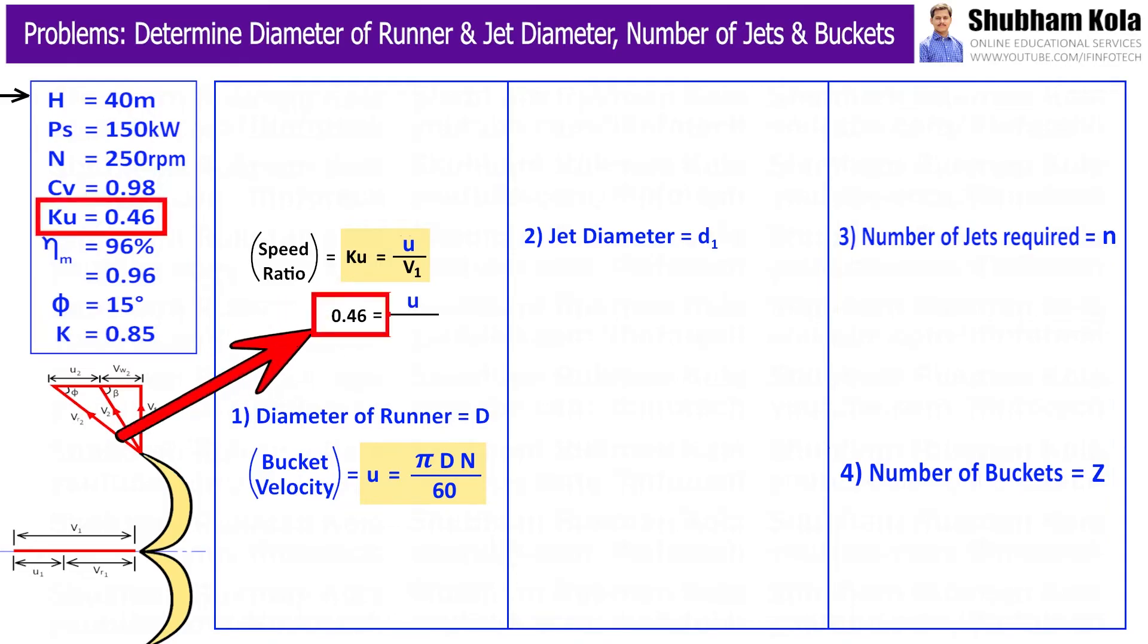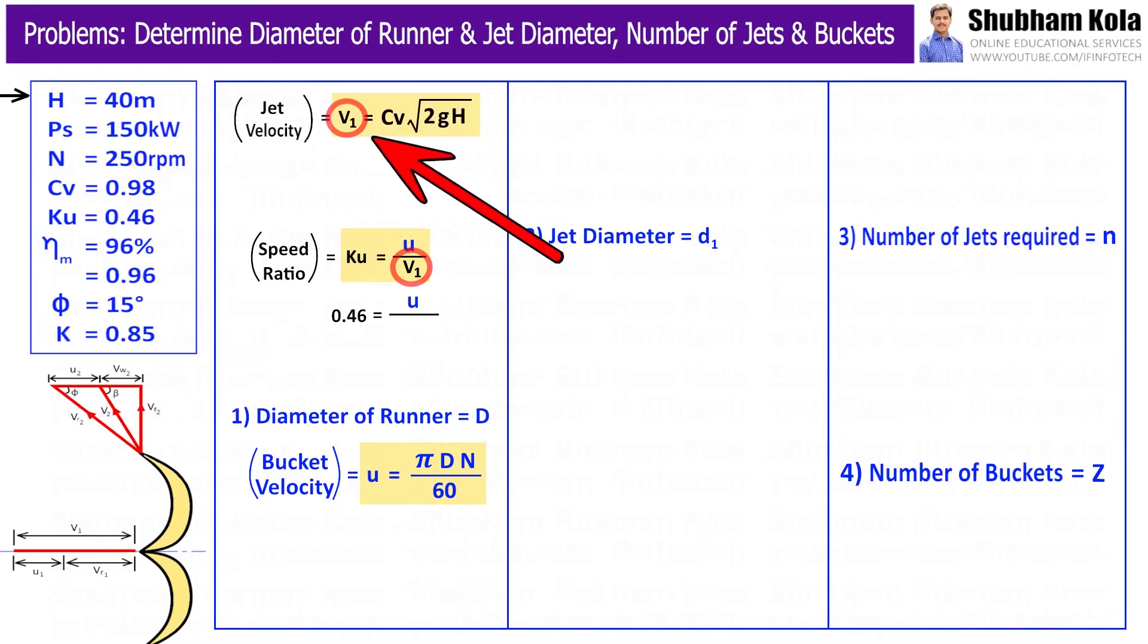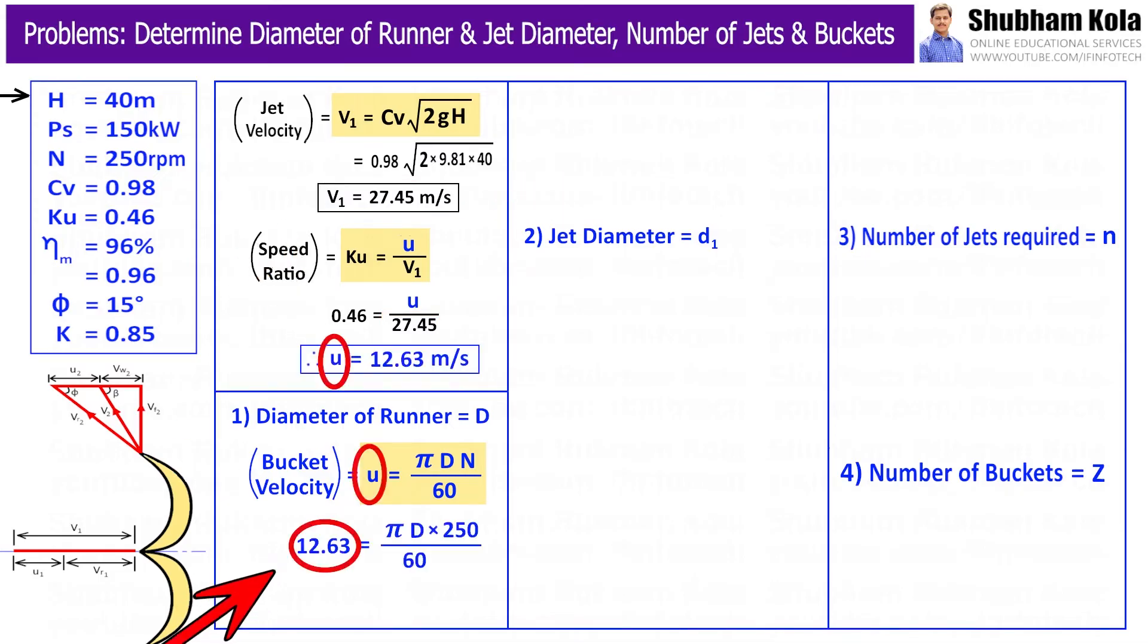To calculate u, we have speed ratio Ku = u/V1 = 0.46, and velocity of jet V1 is given by formula CV√(2gH) where H is 40 meter, velocity coefficient CV is 0.98, and g is 9.81. By calculating, this gives the value of velocity of jet V1 as 27.45 m/s. Substituting bucket speed u and speed N equal to 250 rpm, this gives the value of diameter of runner D as 0.965 meter.